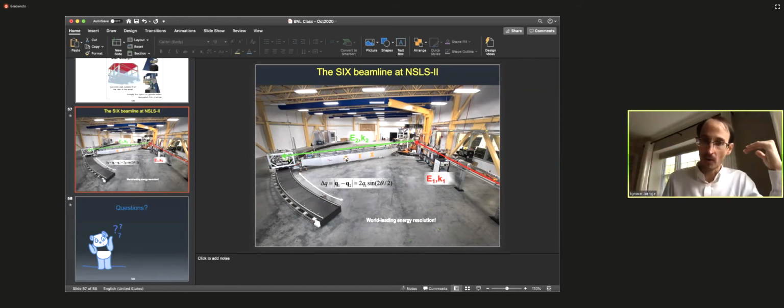When we go in static mode, there's a retraction of the rigid coupling parts. So there's no rigid coupling between this long pipe and the monochromator and the detector. The only points of contact are through bellows, which are soft. So if you have, say, vibrations in the pipe, because it can act as a pendulum, an antenna to some extent, they won't be transmitted that much here and there, because again, the rigid hooks that bring everything together are retracted once the spectrometer stops moving. So it's another way to avoid vibrations in the static mode when we measure.